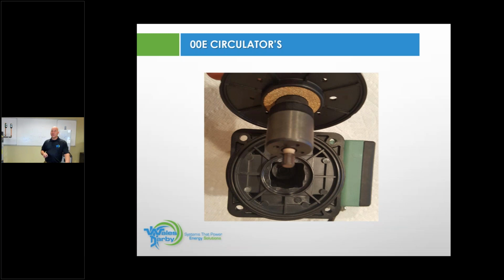And the reason for that bio barrier is we know we have magnetite and all different metals in our heating systems. So we want to make sure that magnetic junk, basically, that's floating around the system does not attach itself to our permanent magnet here. This goes in, and then it's driven by pulses, and we pulse around to drive that magnet, and that's what tells this unit to rotate. So that is what a wet rotor circulator looks like.